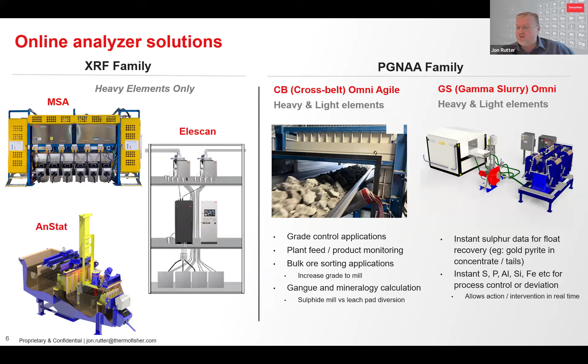We have the centralized analyzers such as the MSA or the multi-stream analyzer. It's great for where you have low headroom or vertical restrictions maybe. Or you have the Elescan that can read up to 24 streams, but it has a smaller XY footprint that will enable it to fit into older analyzer spaces. And then you have the PGNAA family, which can analyze both light and heavy elements, but may have an alternate business use or business case.